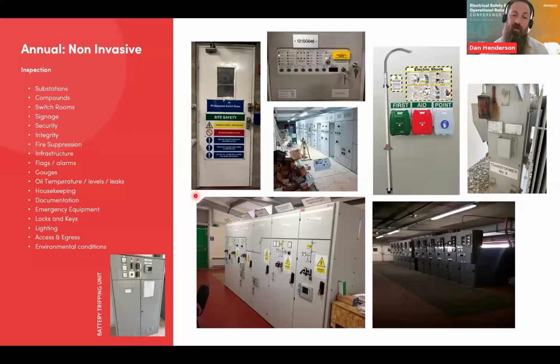Lighting, so make sure you've got suitable lighting in there, and that's something you should check often. These rooms are seldom accessed, and a lot of light fittings go one at a time. You don't really flag it up until there's only one left. So again, it's good to keep on top of that because it's a key contributor to people slipping over or pressing the wrong thing and causing an unplanned operation of switchgear, things like that. So it's good to keep on top of that. Access and egress. Again, always know your escape routes, making sure you've got good clearances in front and behind the gear, especially when you've got withdrawn circuit breakers. The environmental conditions I've kind of mentioned, which brings me to my final point.